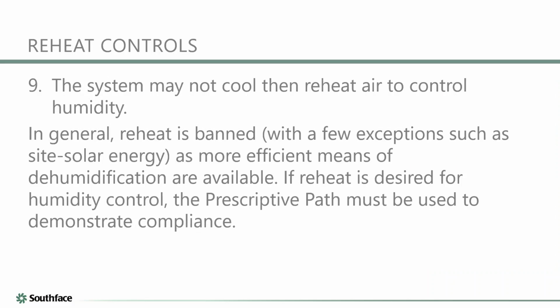All right, another one here, reheat controls. Basically, reheat is a system in which, the way I like to look at it, we supercool the air within the building to dehumidify it, and then we heat it back up for comfortable air temperature. In doing so, we may be able to service different zones at different temperature set points with a centralized system. I like the slide that says, in general, reheat is banned with a few exceptions. If you really need it, like in an archives environment where you need a very specific band of temperature and humidity all the time, then maybe there are some reasons why you would be using something like reheat. But a typical office building probably doesn't need reheat today.